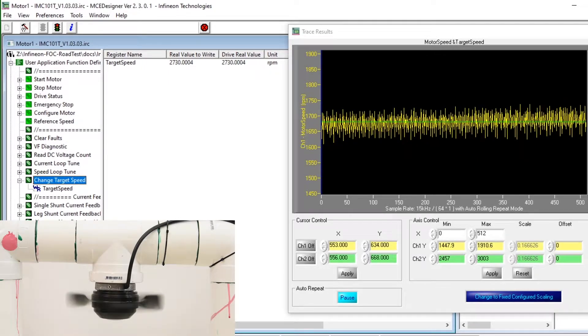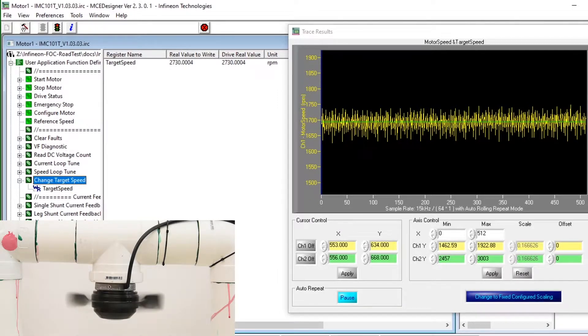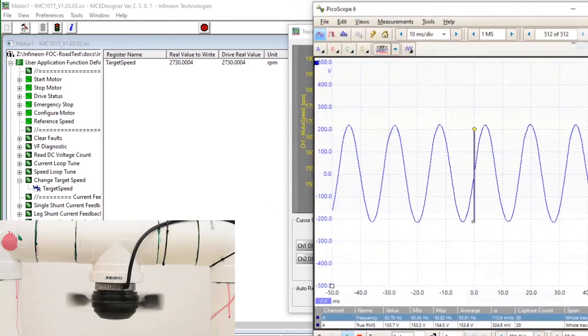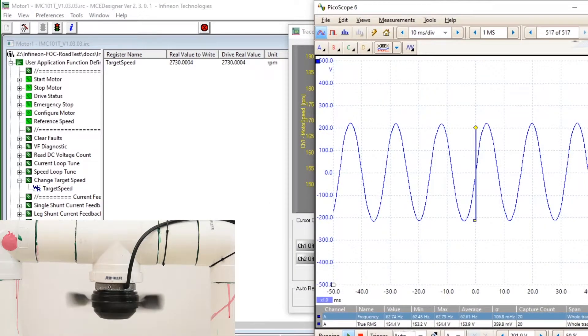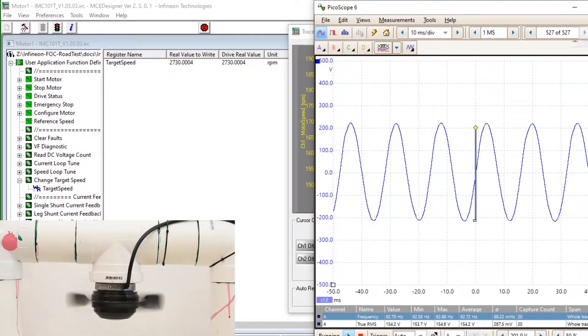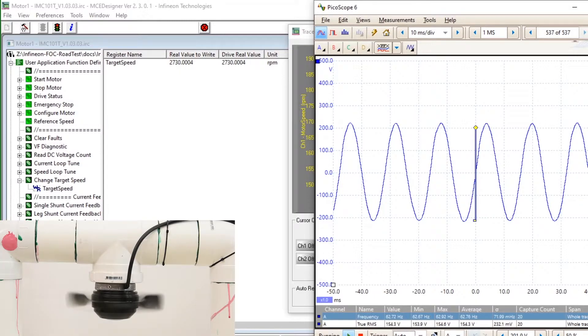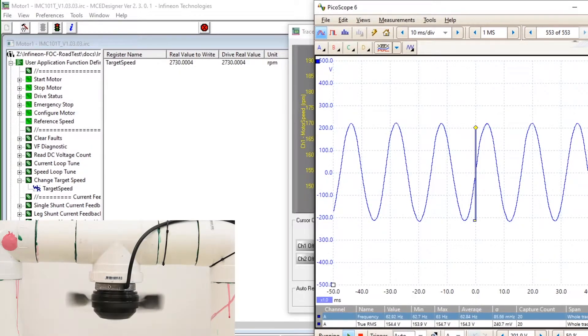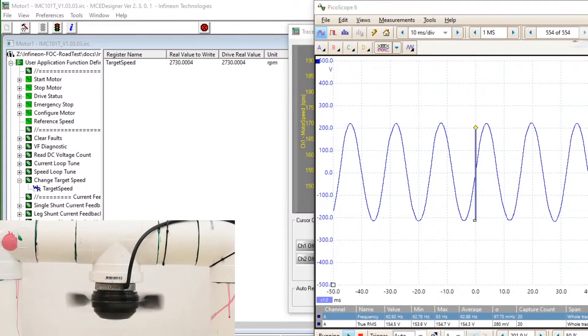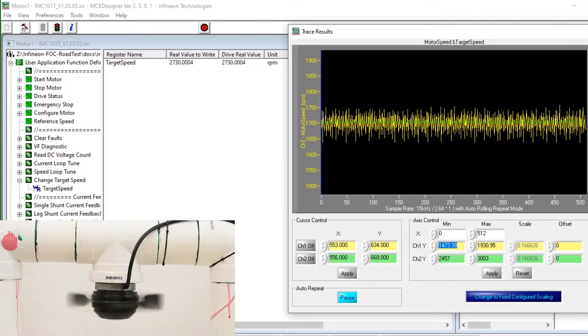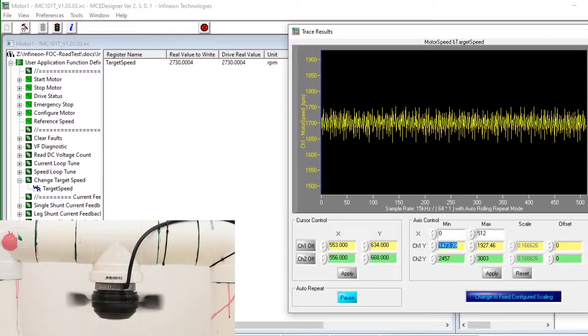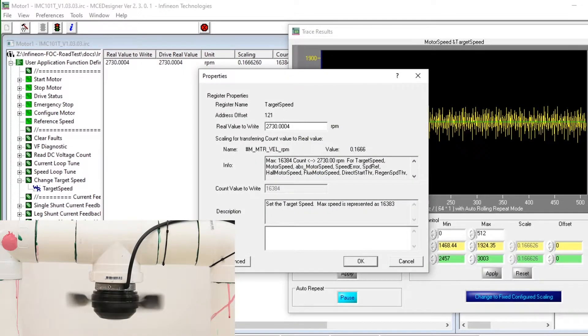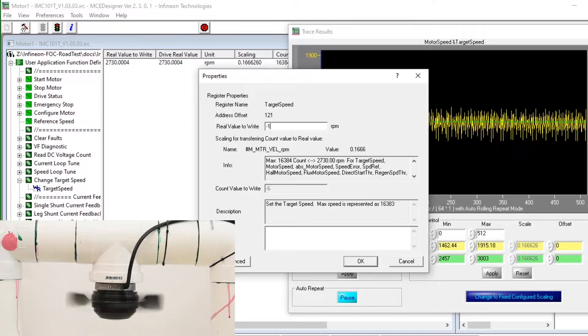The fan speed has now ramped up to a stable speed it claims to be between around 1650 to 1750 estimated rpm. However according to the picoscope trace we can see that we are already over speeding with a frequency of about 62 Hz being applied to the motor which is only rated for 50 to 60 Hz operation.